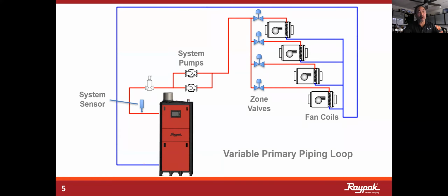If you maintain nice low return water temperatures, you're going to maintain peak efficiency on the boiler. However, one of the things you've got to bear in mind with stainless steel is that it absolutely does require a minimum flow of some type in order to keep the heat transfer proper. When that unit is fired, you want to have a minimum flow. And if you have glycol in the system, that's going to impede the heat transfer. It's going to make the fluid that we're trying to push the heat into more viscous. So consequently, the heat transfer is going to slow down.